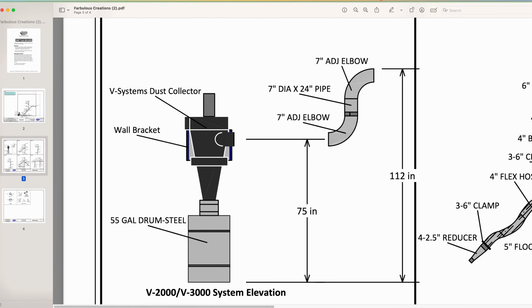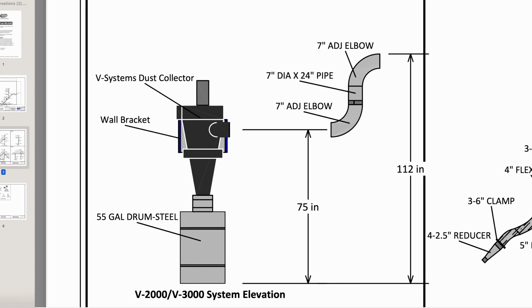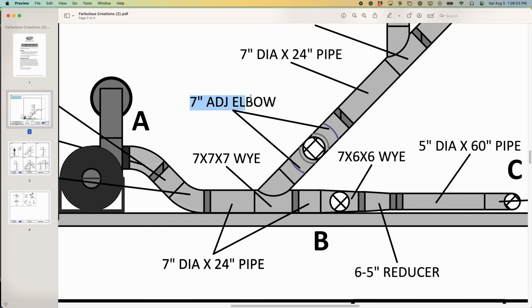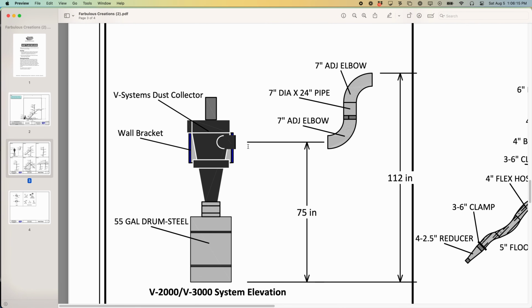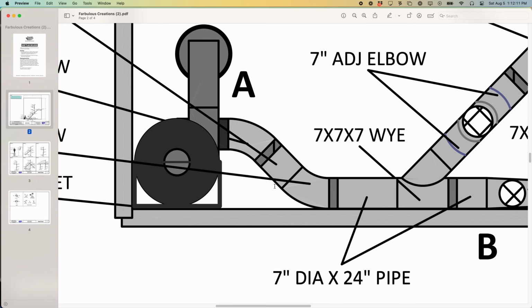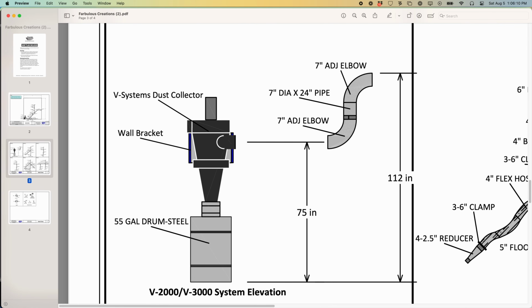The shop diagram's detail view for the area right next to the dust collector is where most of my confusion was, since I recalled us deciding not to go directly up to the ceiling upon leaving the dust collector, but to keep it level with the collector's inlet. This detail view initially seemed to suggest otherwise, but it turned out the elbows shown there actually represented the two elbows shown on the top view, which also explained why they were spaced a bit away from the collector rather than right up against it. The first few elbows were omitted from detail A since they'd be completely horizontal in that view, and detail views are more concerned with changes in vertical elevation.